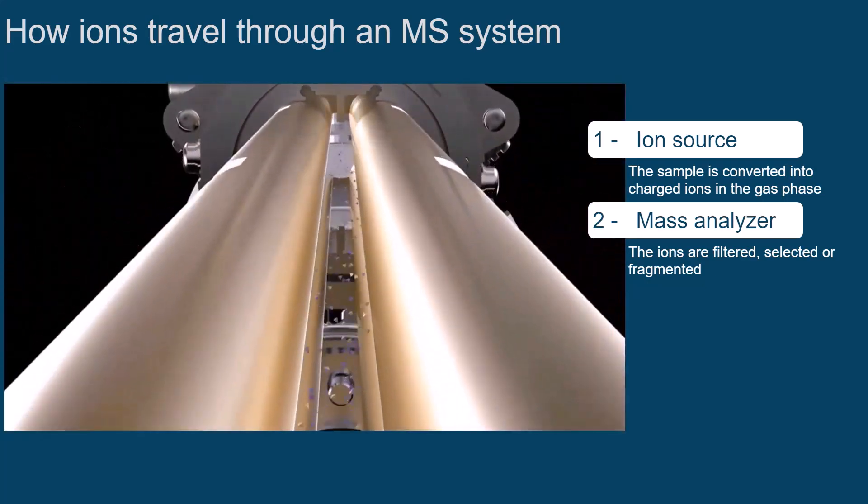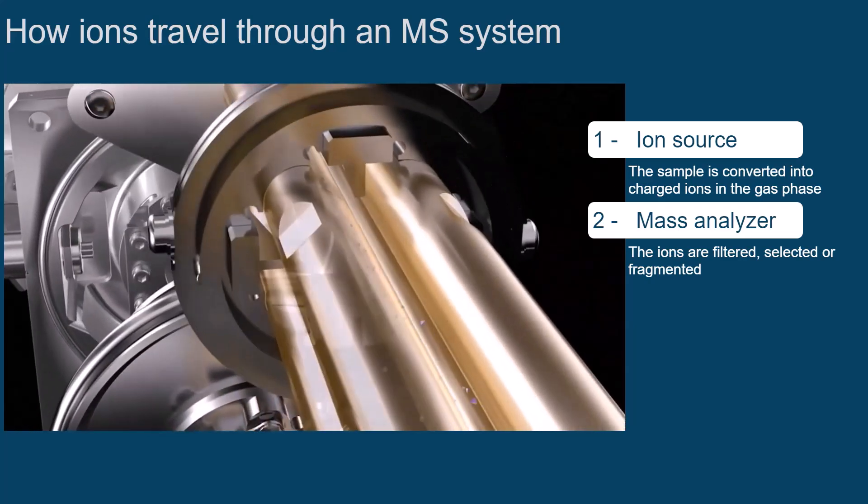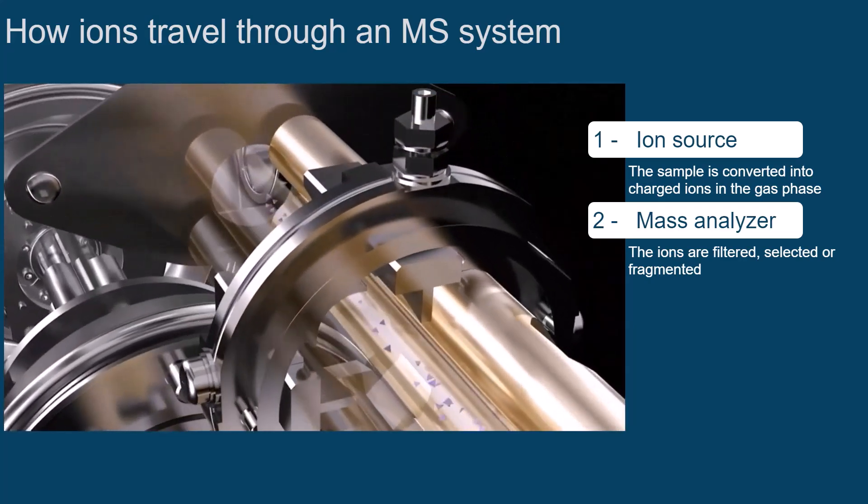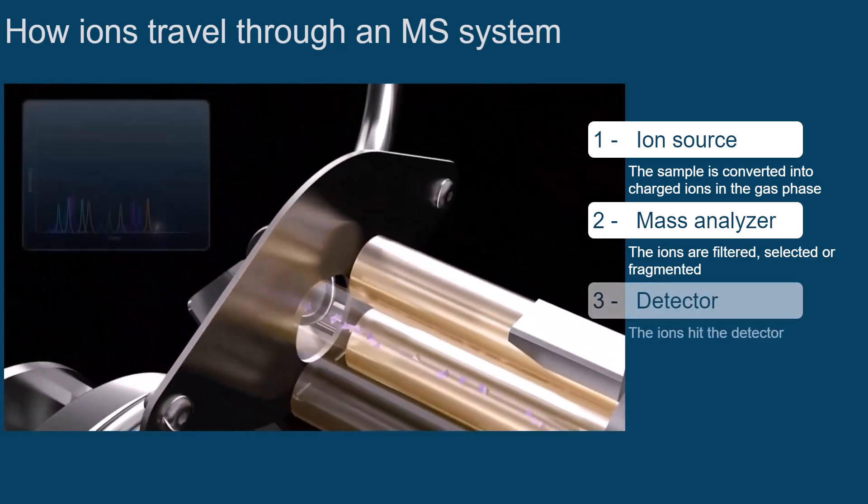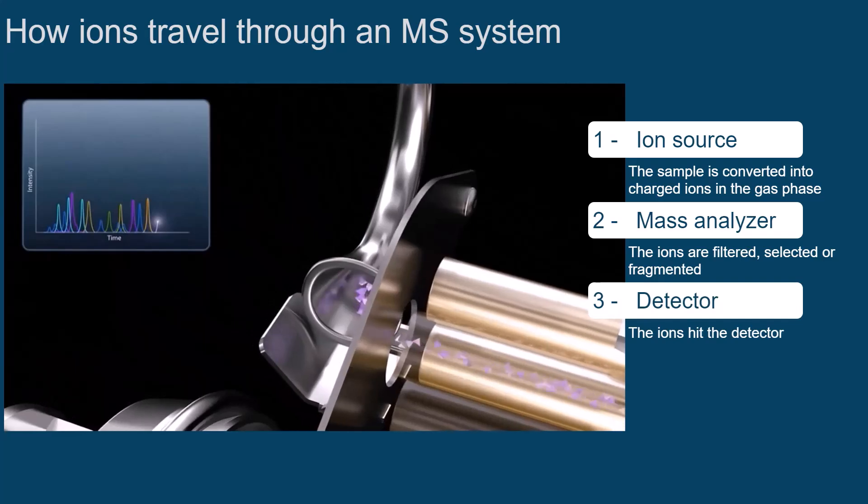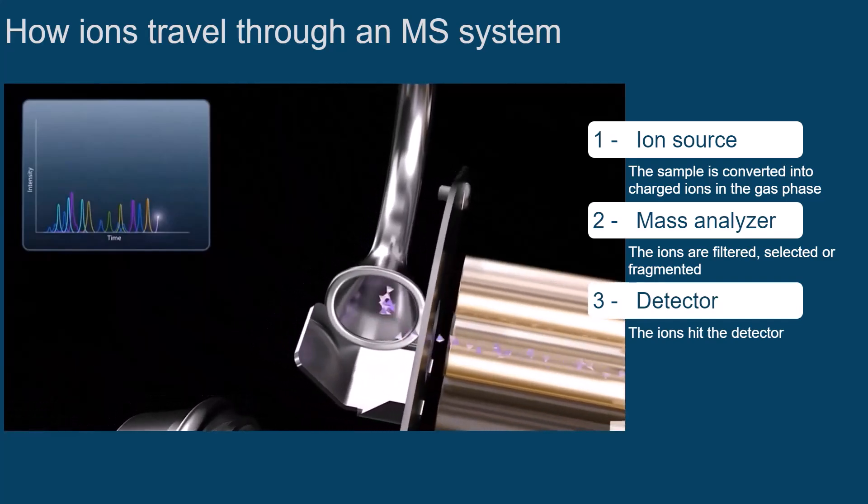In a triple-quadrupole, AC and DC voltages are used to separate ions. After separation, the ions hit the detector. The detector amplifies the signal and sends it to the workstation to convert the information into a mass spectrum.